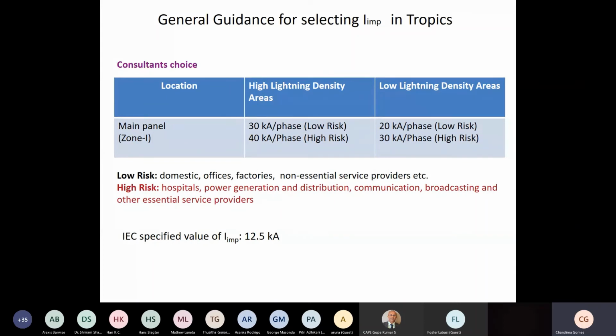But for the last 20 years as a consultant, I have been working in many Southeast Asian countries and African countries as well, especially in the tropics where the lightning density is quite high. What we have seen is that we may need SPDs which have higher current handling capacity than what is specified by IEC. There are arguments, there are debates, okay? So that's why I term this the consultant's choice. So this is what we usually specify.